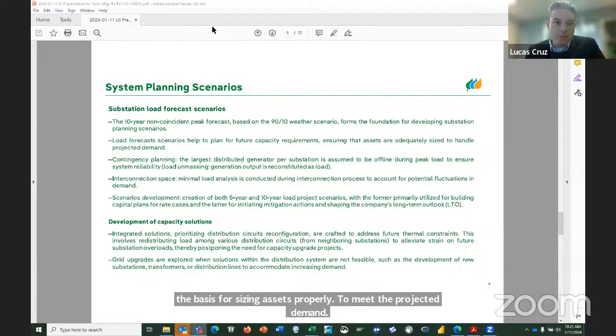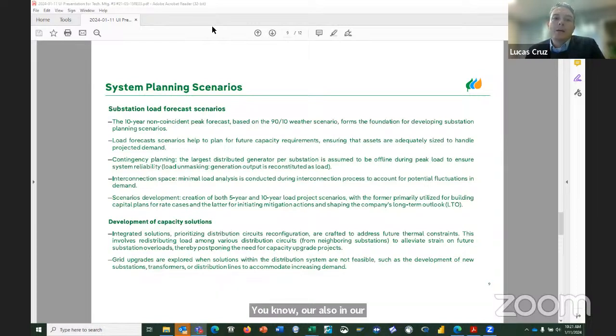In our pursuit of reliability, contingency planning is also considered. We plan for emergencies by assuming that the largest DG at each substation is offline during peak load. With this approach, we basically unmask the loads that are hidden by the DG output, as we reconstitute the DG output as load, making sure we don't rely on a single generation source which is not controlled by the EDC.